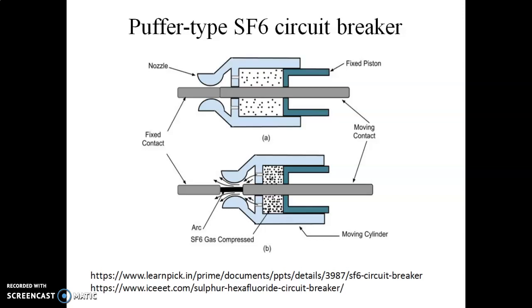See here — single pressure puffer type SF6 circuit breaker construction. A movable cylinder, also known as the puffer cylinder, is placed here. This is the movable part and this is the fixed part. The arrangement of the fixed and moving contacts is shown in the first figure and second figure. The first figure shows the normal condition where the two contacts are in the closed position.